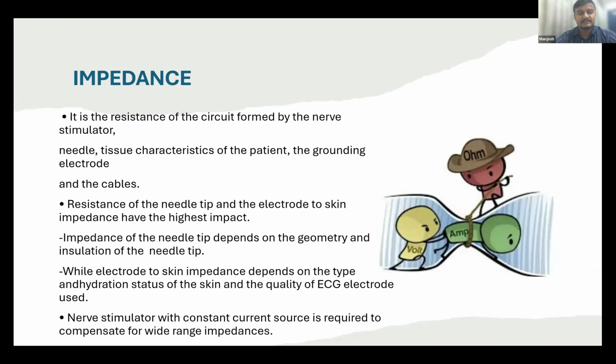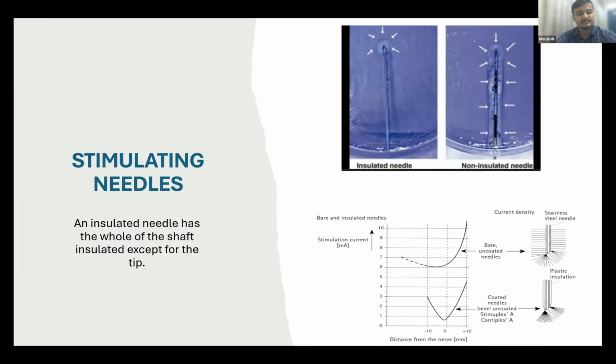And coming to the concept of impedance, it is the resistance of the circuit formed by the nerve stimulator and needle, the tissue characteristics of the patient, the grounding electrode, and the cables. Usually the grounding electrode we use is the ECG electrode. The resistance of the needle tip and the electrode-to-skin impedance have the highest impact. Impedance of the needle tip depends on the geometry and insulation of the needle tip, while electrode-to-skin impedance depends on the type and hydration status of the skin and the quality of the ECG electrode used. And the nerve stimulator with constant current is required to compensate for wide range impedances.